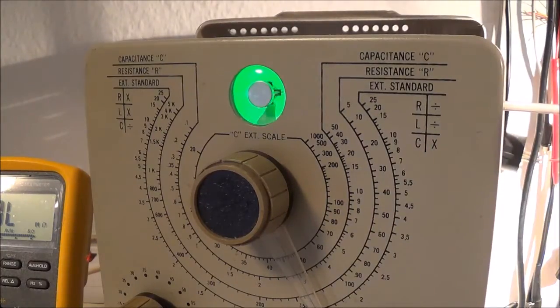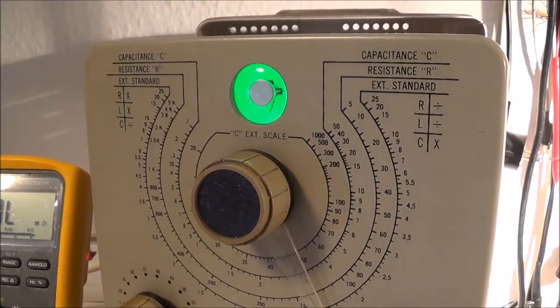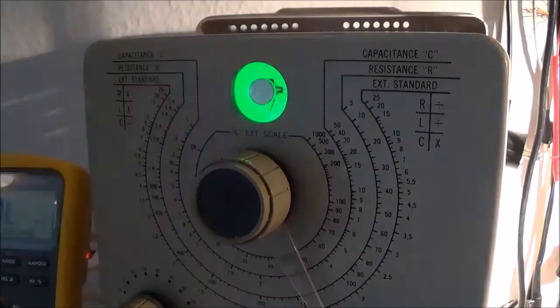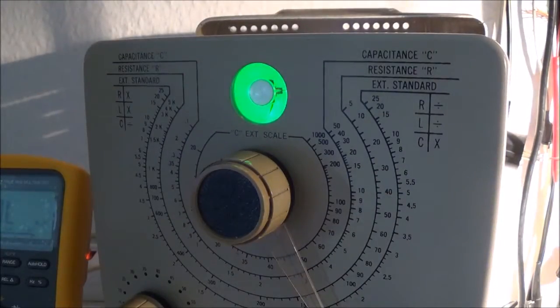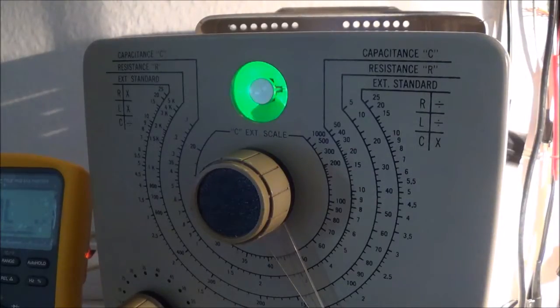I thought there was nothing happening. So the just closed position, that might be like right around there I guess. So that was that. Now I go to the next calibration. I have to move the bridge leakage switch to discharge and remove the 100 kiloohm resistor, and then I connect a 1.5 megaohm resistor across the test terminals for the next step.